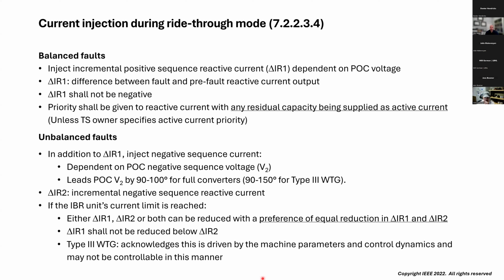And then if we reach the current limit during these unbalanced faults, the preference is really an equal reduction of the incremental positive sequence reactive current and the incremental negative sequence reactive current. There are some other approaches that are okay per the standard, but in any of these approaches, we can't reduce the incremental positive sequence reactive current less than that of the negative sequence.